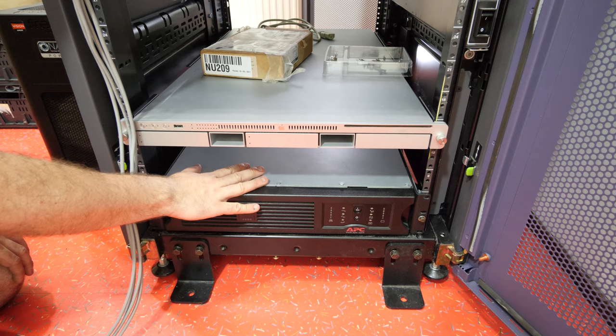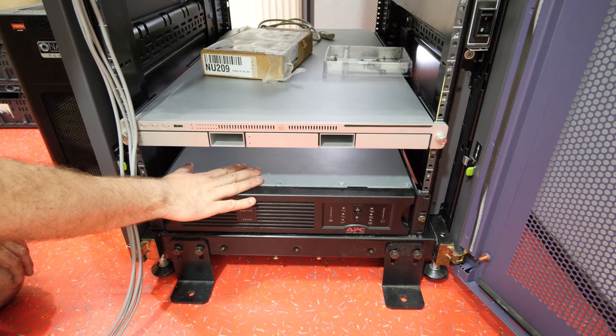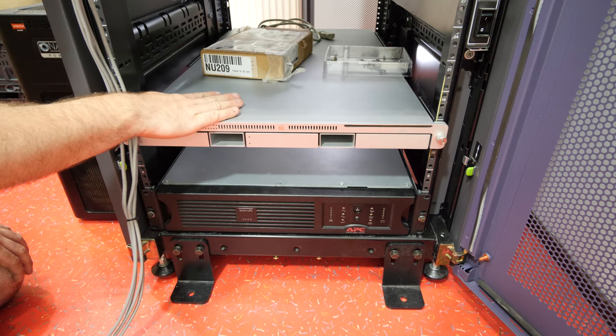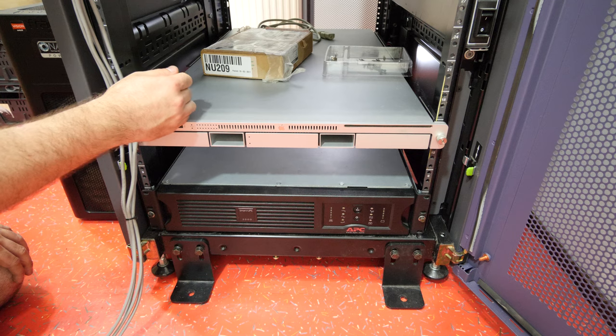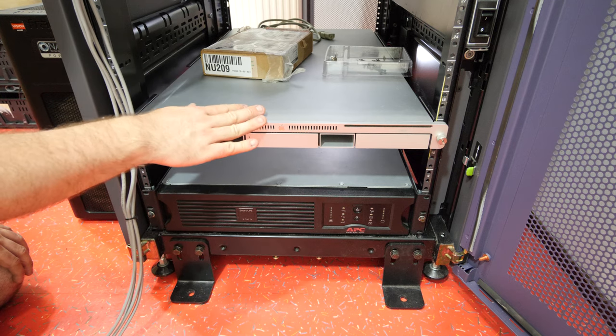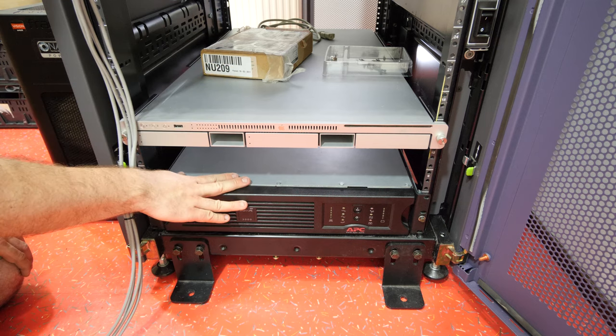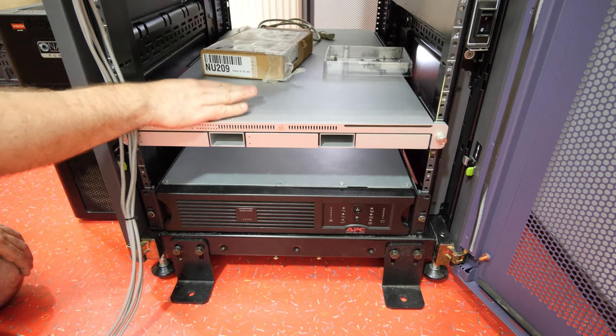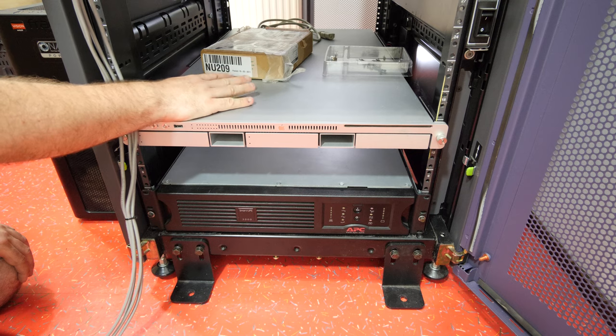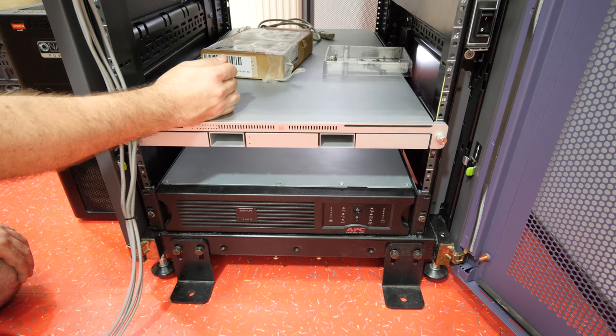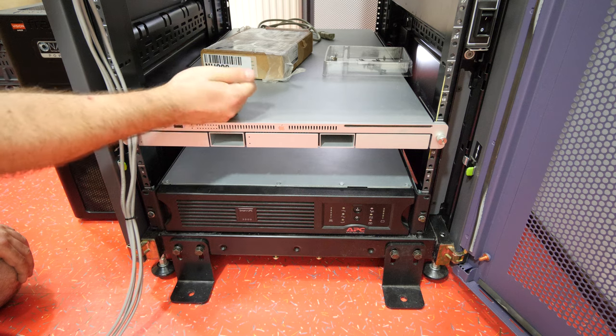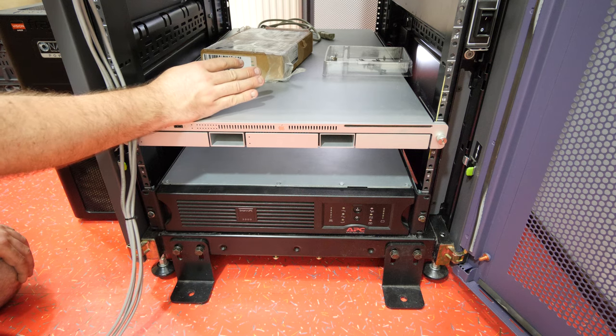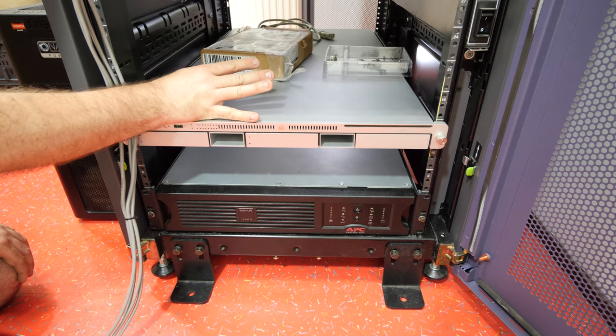The UPS batteries are broken. I plugged in the UPS for like 12 hours, then I put the Apple X-Serve as a load on the UPS. I pulled out the cable and it was immediately shut down from both the UPS and the server. I let the UPS recharge a bit, tried it again without turning on the server. But still the power supply is running when you plug in the power. I pulled out the power plug and it got like 40 seconds before it was dead.